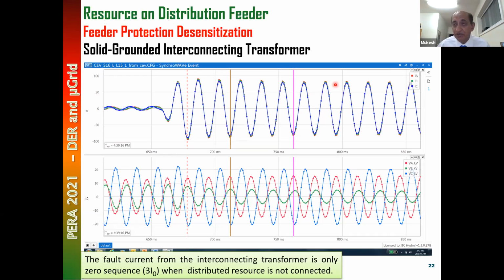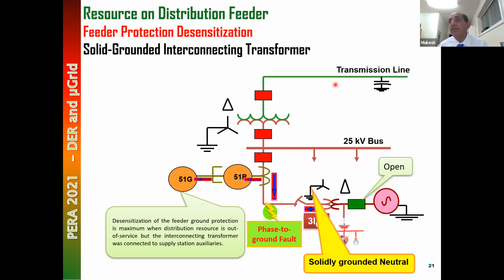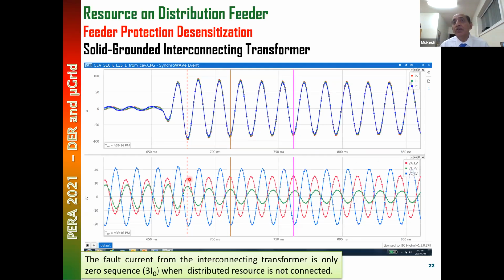That's why this transformer has another name. There's a second name for this transformer. This transformer is also called a zero sequence source. It is not a positive sequence source. The positive sequence source is disconnected and it supplies a zero sequence source. So it's a ground fault. One phase voltage is low, the other phase voltage is low. There's an explanation; I will defer that one. So the transformer is a zero sequence current source here.